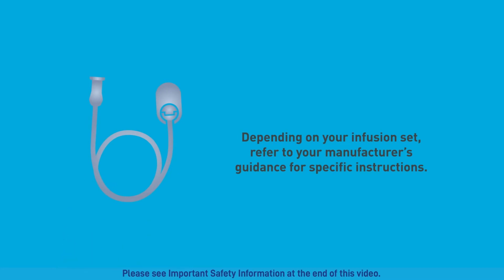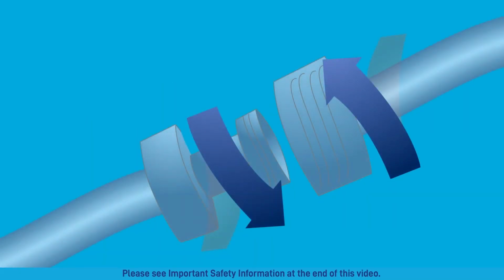Once the connector cap has been removed, open your infusion package and take out the infusion set. Connect the infusion set and cassette by twisting the lock connectors together. Do not insert the new infusion set catheter into your body until after you have prepared the new cassette and connected it to the pump. Inserting the infusion set catheter before connecting the cassette to the pump may lead to unintended delivery.